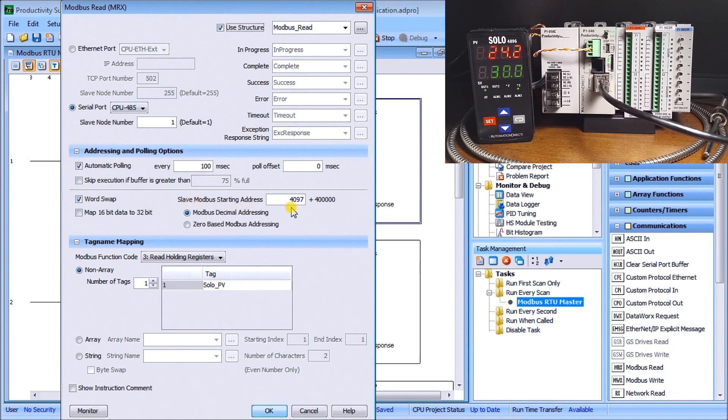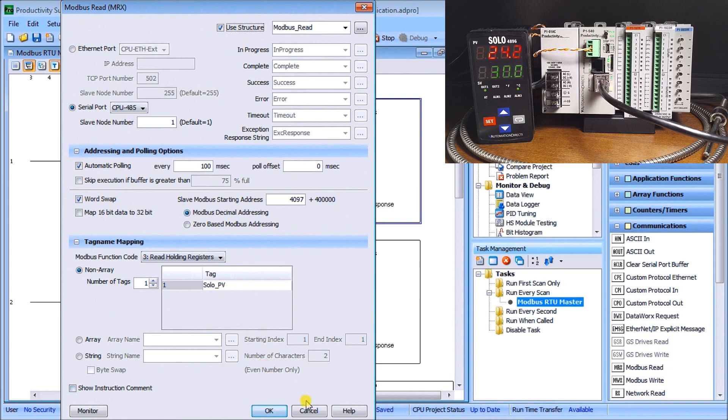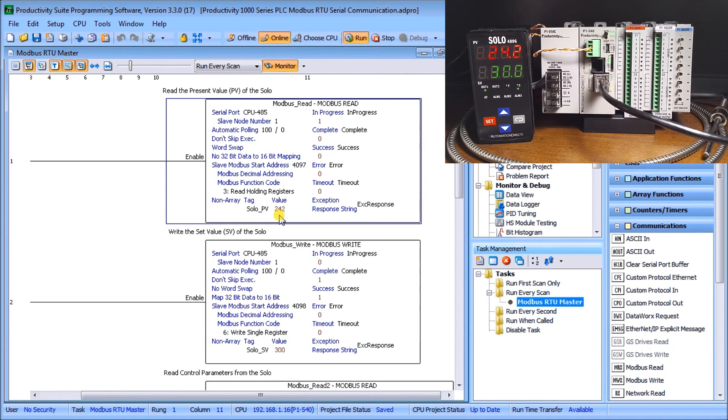We have our master slave starting address which is 4097 and we're using the modbus decimal addressing. We have a number of tags just one and we're going to read the solo present value or PV value. You can see here that I'm running and our present value currently right now is reading in at 24.2 which is exactly what it's saying on my solo.